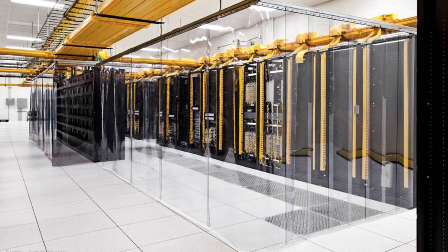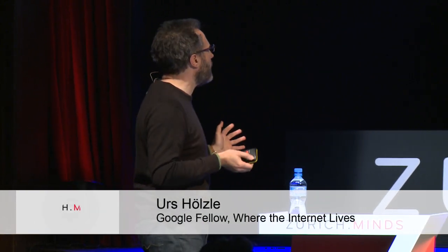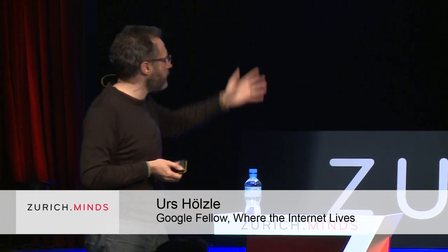Another key thing here, this is a picture of a server room where we have commercial gear that has some more restrictions. So we have a slightly different setup, but you see that there are these plastic curtains in here. And these plastic curtains separate the space that should be cold or cool, 27 degrees, from the rest of the space that can be arbitrarily warm. In this particular case, this is a more traditional place where we host some networking gear. You see the cold air coming out of the floor, but these curtains keep it in front of the machines that actually need the cold air and prevent it from going out. And that again saves lots of energy.